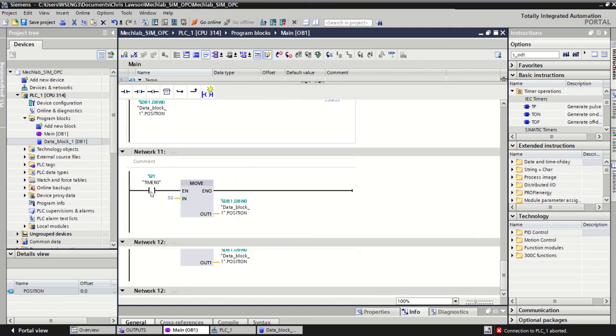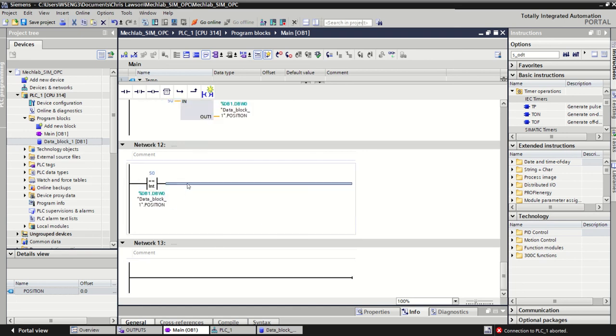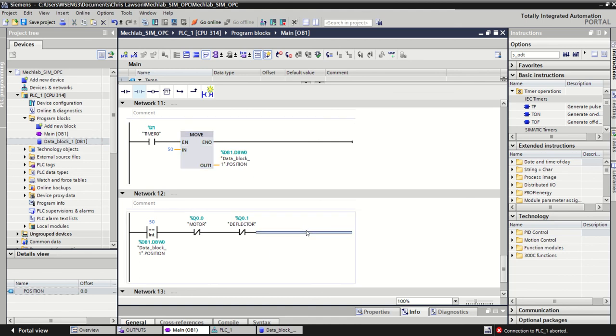So what we just do is we say, all right, when we're in step 50, just do a wee check for me to make sure: has my motor gone off? So is my motor off? Is my deflector off? And then if that is correct, go ahead and move 0 back in. So that's using the outputs as a reference, because again we've no input that tells us when the motor is on or off, or the deflector is extended or retracted. So we're just looking, is the output on or off? So that's that little trick again, just showing you how we can use the outputs as inputs for reference.